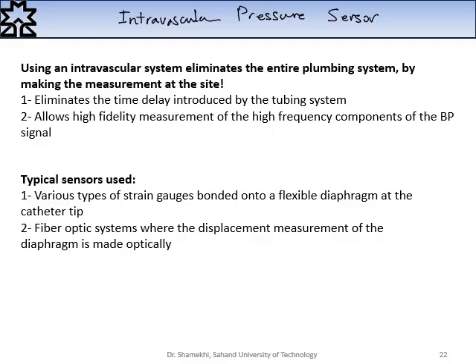Using an intravascular system eliminates the entire plumbing system by making the measurement at the site, as we mentioned before. It eliminates the time delay introduced by the tubing system, and also allows high fidelity measurement of high frequency components of the blood pressure signal. For intravascular pressure sensors, we have two types of sensors. We can use various types of strain gauge bonded onto a flexible diaphragm at the catheter tip, and we can also use fiber optic systems where the displacement measurement of the diaphragm is made optically.